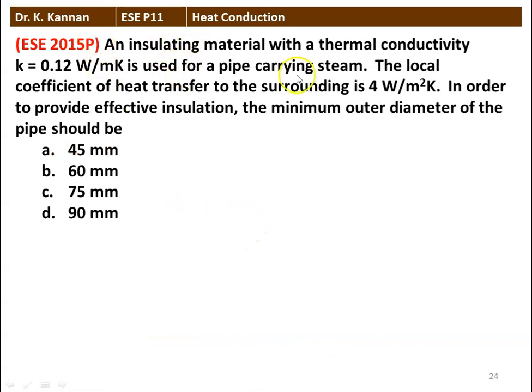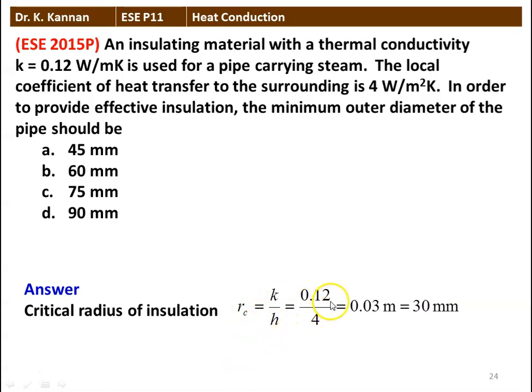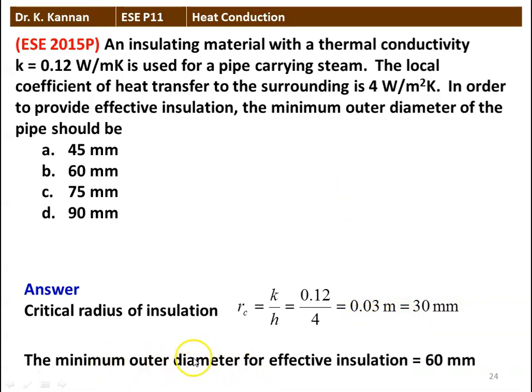Next question: an insulating material with thermal conductivity K = 0.12 watts per meter Kelvin is used for a pipe carrying steam. The local heat transfer coefficient to the surrounding is 4 watts per meter square Kelvin. In order to provide effective insulation, the minimum outer diameter of the pipe should be: (A) 45 mm, (B) 60 mm, (C) 75 mm, (D) 90 mm. The critical radius RC = K / H = 0.12 / 4 = 0.03 meter = 30 millimeter. The minimum outer diameter = 2 × RC = 60 millimeter. The answer is option B, 60 millimeter.